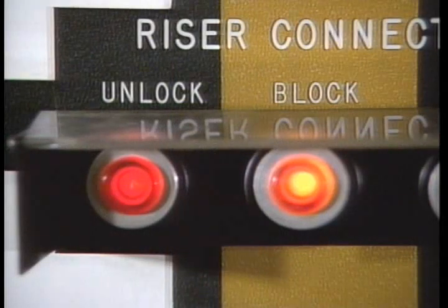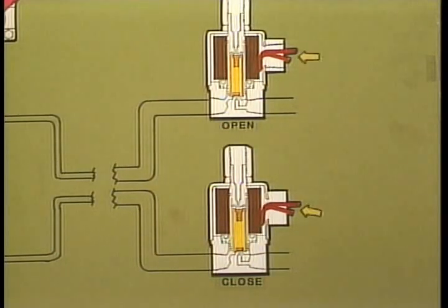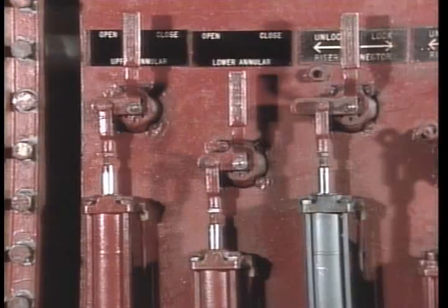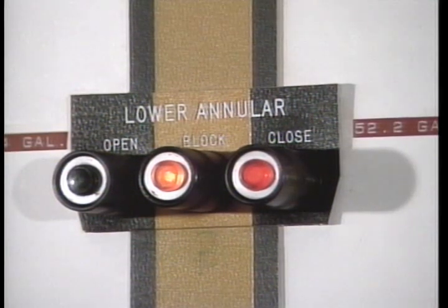In explaining the operation of the block button, there are two possibilities. First, the Koomey system manufactured by NL Shaffer: pushing the block button completes a circuit sending voltage to both the open and closed solenoids. Both solenoids open and allow rig air to act on both the piston end and rod end of the three-position air cylinder, moving the rod halfway between fully extended and fully retracted. The four-way valve, via the mechanical linkage, is forced to the center or block position. The block button indicator light turns on as a result of pressure being removed from both the open and closed pressure switches simultaneously.